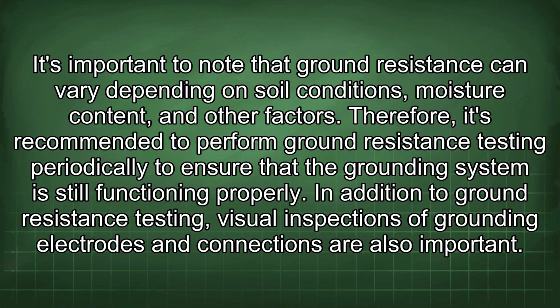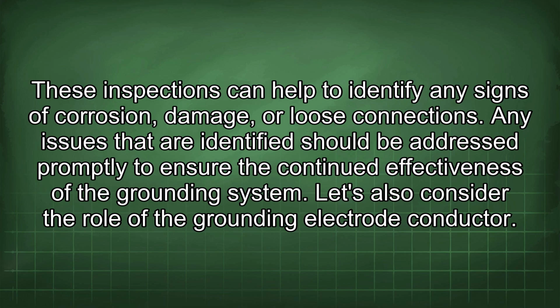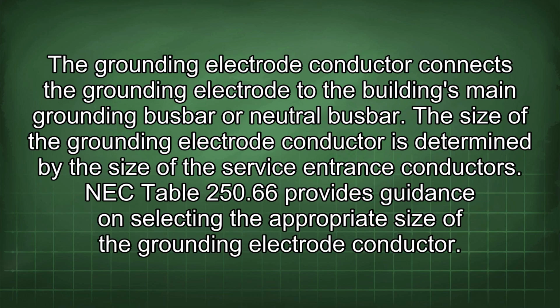In addition to ground resistance testing, visual inspections of grounding electrodes and connections are also important. These inspections can help to identify any signs of corrosion, damage, or loose connections. Any issues that are identified should be addressed promptly to ensure the continued effectiveness of the grounding system. Let's also consider the role of the grounding electrode conductor. The grounding electrode conductor connects the grounding electrode to the building's main grounding busbar or neutral busbar. The size of the grounding electrode conductor is determined by the size of the service entrance conductors.